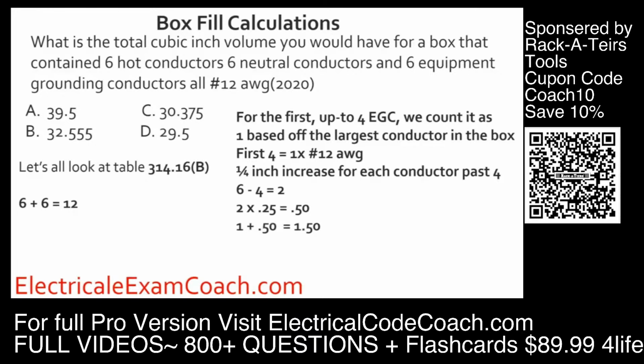Then we have our 1 original. Then we have 0.50 add-on, so that gives us 1.50 grounds. We need to take and add that back to the 12, so we take our 12 plus our 1.50, then we multiply that by the individual volume for a number 12, which is 2.25, and we end up with 30.375.